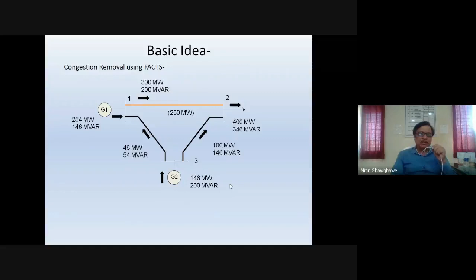So if I use TCSC over here in lines 2 and 3, thyristor controlled series capacitor, what exactly does this TCSC do? It reduces the reactance of the entire line. TCSC is basically a series capacitive reactance which is controlled by the firing angle, right? So this reactance can be controlled. When TCSC, XC, is introduced in a line, it has a negative value, negative reactance. When it is added to the inductive reactance of the line, the total reactance of the line will be decreased.